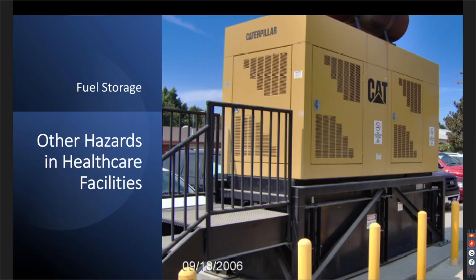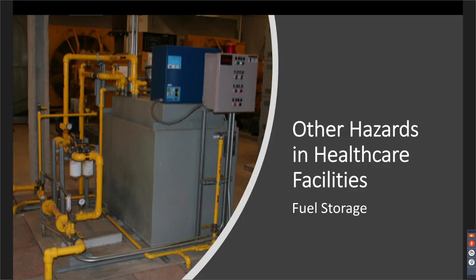With the generators come fuel storage, and from a fire protection standpoint, fuel storage for combustible and flammable liquids is always problematic. It's always challenging. The building code regulates fuel storage by limiting the total capacity of fuel storage that you're allowed to have within the buildings. This particular case is a day tank that may be a 60-gallon tank. Is that okay? The answer is maybe. It really depends on where this particular tank is physically located.